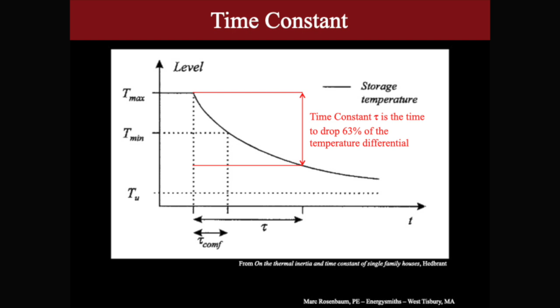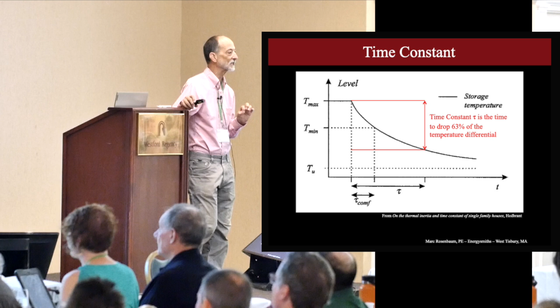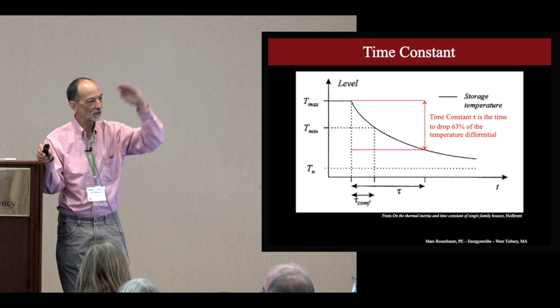Okay, so if you don't put any heat into this building and you let it coast down to TU, at the point where it has dropped 63% of that differential, and that has to do with logarithms, and I'm not going to explain that, that's the time constant, the time it took to drop 63% from the original temperature to the outside temperature. Hold that thought. So what is a building time constant? You can calculate a building time constant: the thermal capacity of the building divided by its heat loss coefficient.